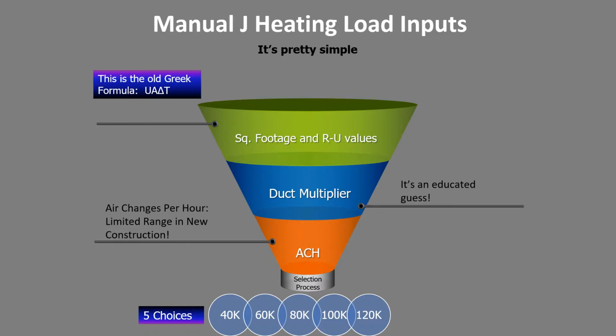So basically what you do is you get the square footage, you look at the area and the U values. You get a duct multiplier, and duct multipliers, even if you do a duct leak test, is an estimate. If you don't do one, it's an educated guess. Air changes per hour, homes have certainly got a lot tighter. And when you're doing that, for any kind of furnace, you end up with 4 or 5 basic choices.